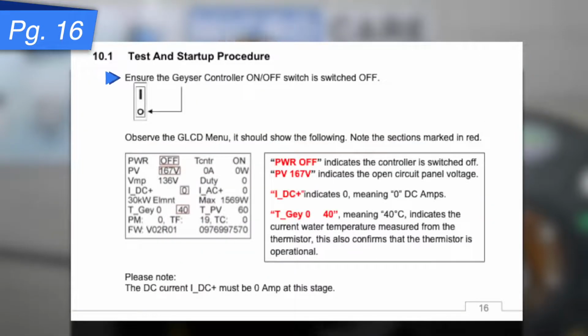So 10.1, ensure the geyser controller on-off switch is still off at this point. We've only switched on the isolator and the separate DC disconnect switch. And if you look at the screen at the bottom of page 16, it says there, power off. This is a snapshot of the GC LCD. It will say power off, and for the PV, you should be reading voltage there. If you're reading voltage there, then that's correct. So these are the things that you're looking for at the bottom of page 16 on that GC LCD.